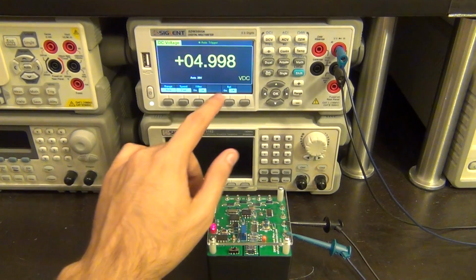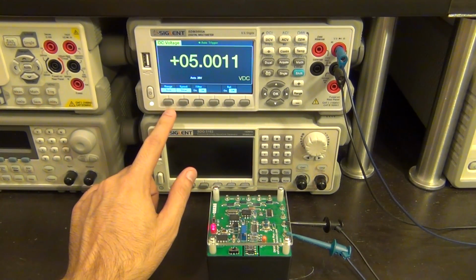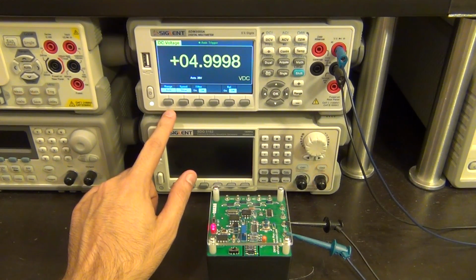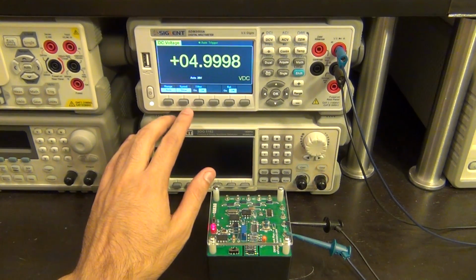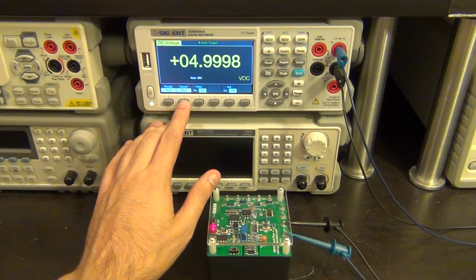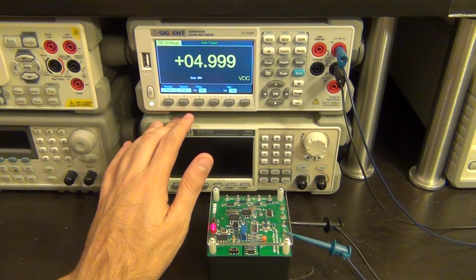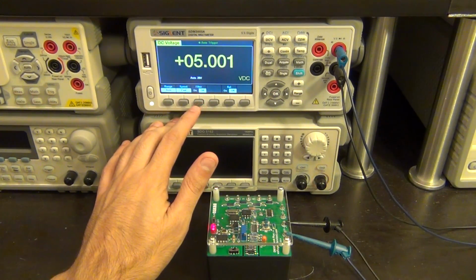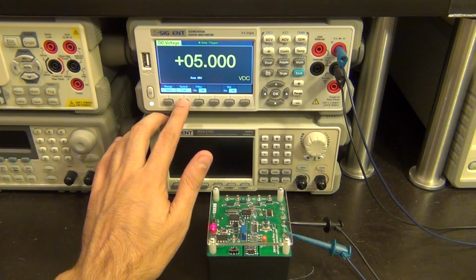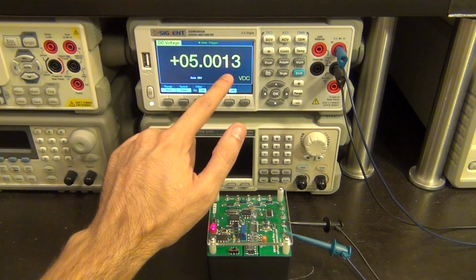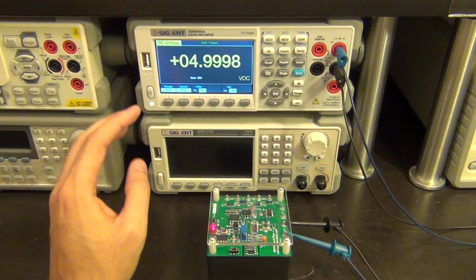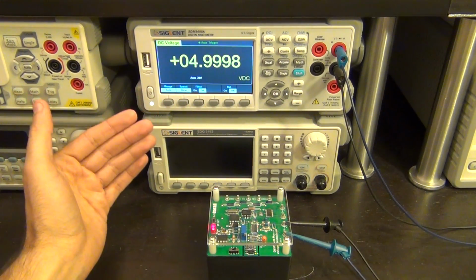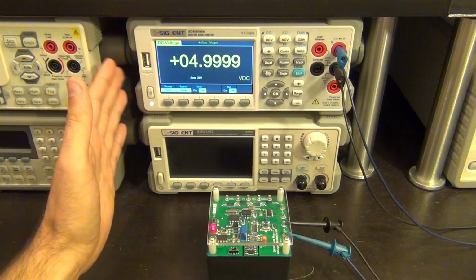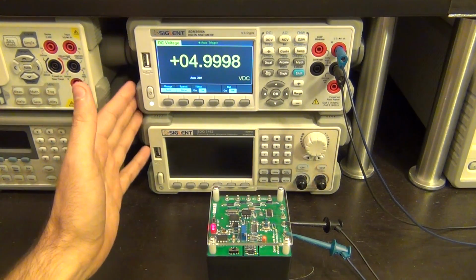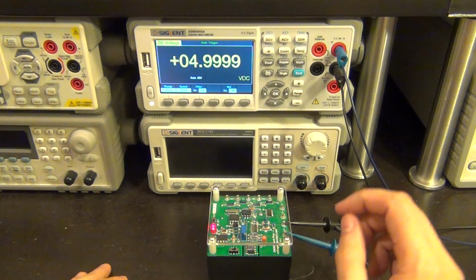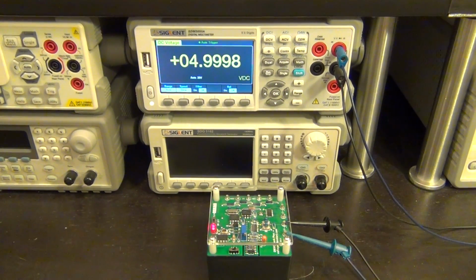One thing I noticed is that when I put it onto the slow mode, it takes a little bit of time before the measurement result from the fast condition disappears from the screen. If I go to fast, you can see the 5 volt, and now it says there's a 1 at the very end. When I go to slow, you can see it carries that with it, and then it updates. In reality, it should display nothing before it displays the other value. Or maybe I'm nitpicking here, but it's important because you can cause confusion when doing a quick measurement. So there's our 5 volt measurement. Let's measure current.